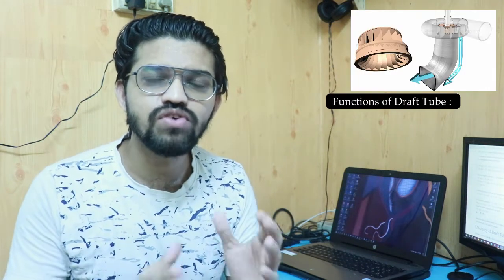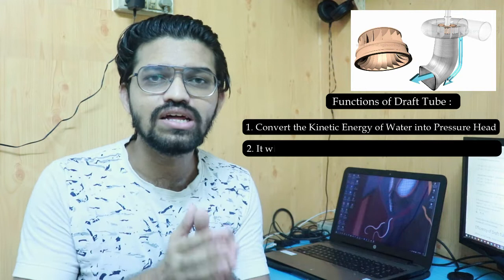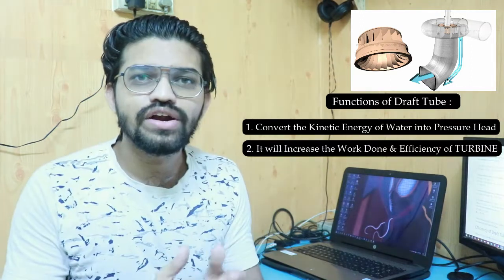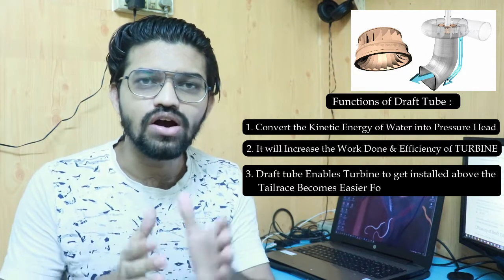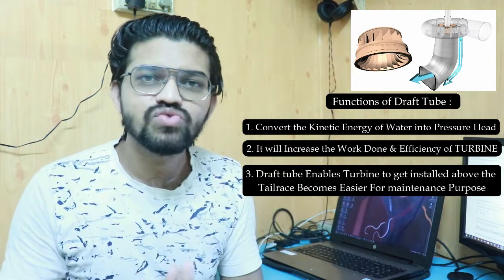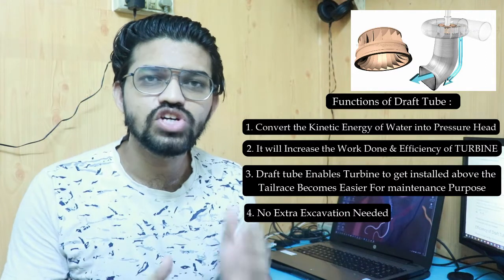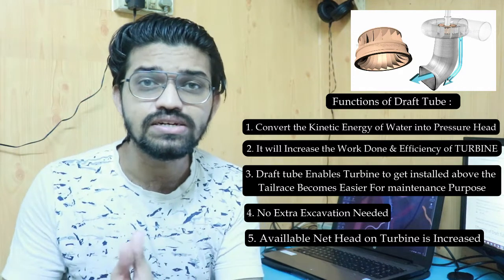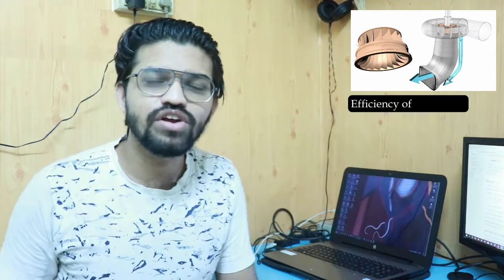The draft tube has different functions. First, it converts the available kinetic energy of the water into pressure head. It also increases the efficiency of the turbine and the total overall work done on the turbine. The draft tube enables the Francis turbine or reaction turbine to be installed above the tail race, which makes maintenance and repair easier, and no extra excavation is needed. Also, the available net head on the turbine is increased because of the draft tube.